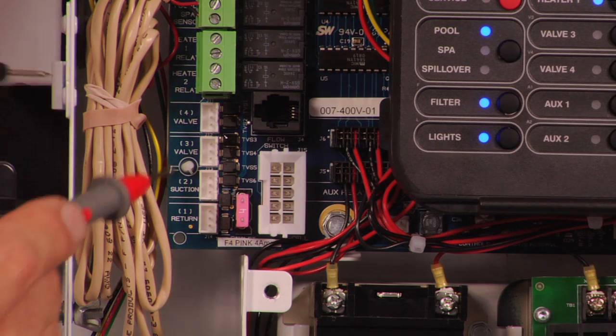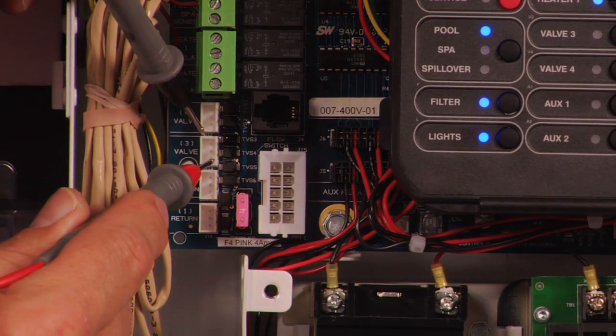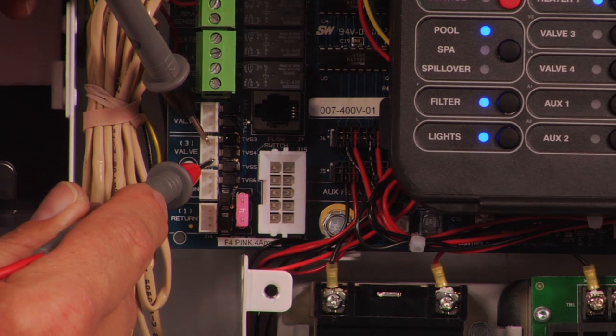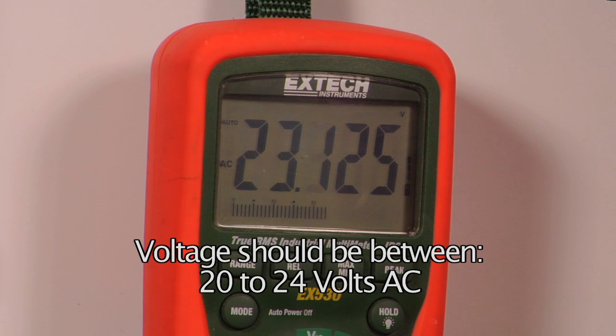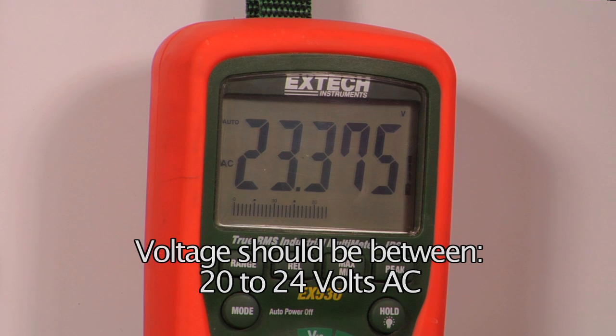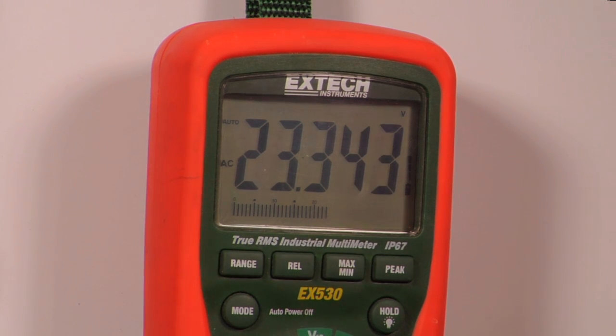If the actuator is turned off, the reading between the lower pin and the upper pin will be 20 to 24 volts AC. If there is no voltage reading, the main board is bad and needs to be replaced. If there is a voltage reading, the valve actuator is bad and needs to be replaced.